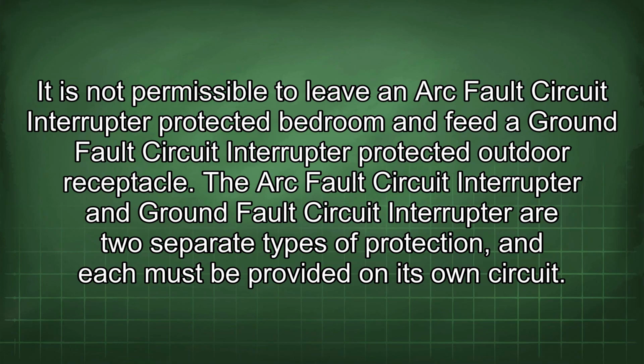It is not permissible to leave an arc fault circuit interrupter protected bedroom and feed a ground fault circuit interrupter protected outdoor receptacle. The arc fault circuit interrupter and ground fault circuit interrupter are two separate types of protection, and each must be provided on its own circuit.